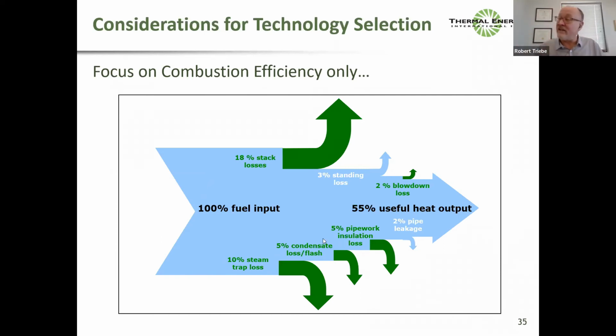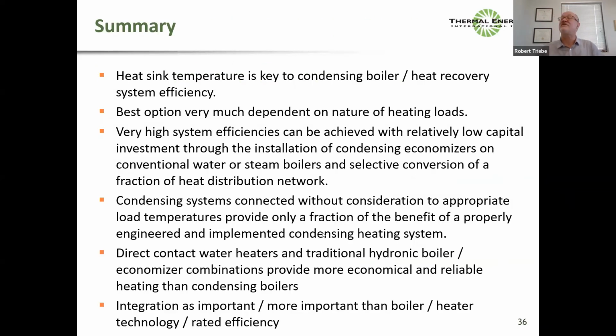However, then you're not dealing with all of this stuff. Because you still got steam going through the plant, you've still got leaks, you've still got a higher temperature heating system, which means more radiation losses. You've still got steam traps, which are difficult and a nightmare, blow down. So if you want to just try and get your steam plant thermal efficiency way up there, you can have condensing efficiencies by just adding an economizer. The same boiler efficiency as any condensing boiler you can have with a steam boiler and a condensing economizer. But of course, that doesn't eliminate the rest of the issues with steam moving through a facility. So just another consideration when you're looking for your savings in your project. So summary.